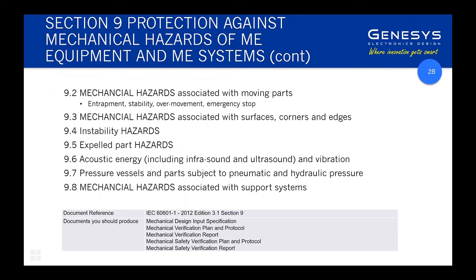There are specific categories of hazard including acoustic energy. Many sections are quite specific to different equipment types, added as new medical equipment has come to market. A recurrent theme throughout: you should have specifications for everything, verification and validation plans and reports to show you've addressed these hazards, and reports from accredited test labs — not just in-house engineering reports — so they carry more weight in the assessment process.